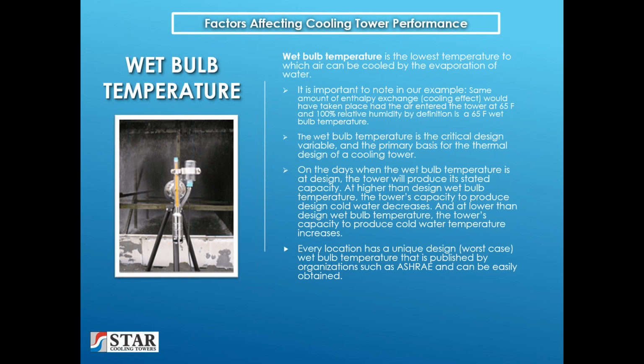Every location has a unique design or worst case wet bulb temperature that is published by organizations such as ASHRAE and can easily be obtained. For cooling towers, typically the design frequency level is 1%. Here's an example of some published data on the wet bulb temperature. If we look at Port Arthur and we come over and we see a 1% frequency level, is at 80.8 degree wet bulb temperature.